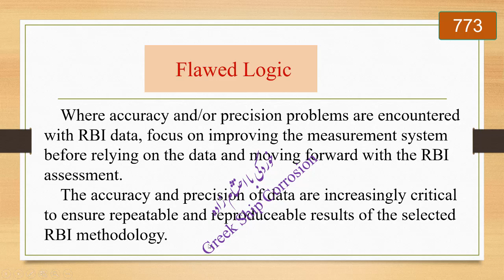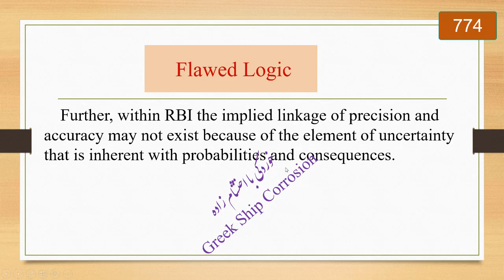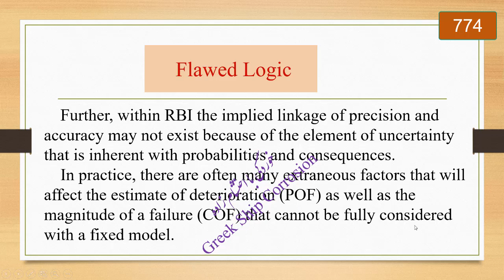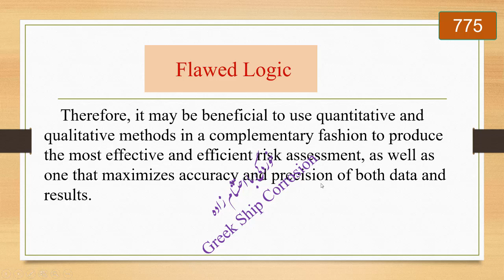Further, within RBI, the implied linkage of precision and accuracy may not exist because of the element of uncertainty that is inherent with probabilities and consequences. In practice, there are often many extraneous factors that will affect the estimate of deterioration or POF, as well as the magnitude of a failure, COF, that cannot be fully considered with a fixed model. Therefore, it may be beneficial to use quantitative and qualitative methods in a complementary fashion to produce the most effective and efficient risk assessment, as well as one that maximizes accuracy and precision of both data and results.